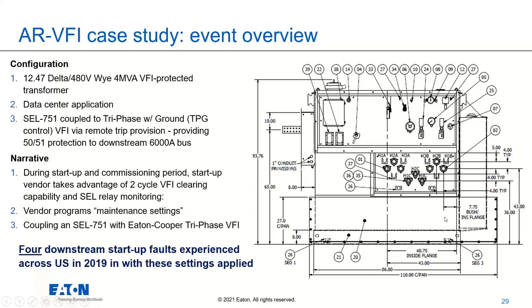And the huge benefit from a commissioning perspective is this is all functionally verified at the factory. There isn't any need to tie my relay to my breaker or tie my CTs back to the relay, or questions about what size or components I have. Any of those questions that can come up when you're designing, implementing, commissioning or testing a protection system can all be handled by an integrator or a manufacturer. So in this case, we had our 12470 to 480Y 4MVA transformer with a 6,000 amp bus coming off the secondary. So lots of energy present there that's capable of coming out of this transformer. But we do have that integrated system that I was referring to.